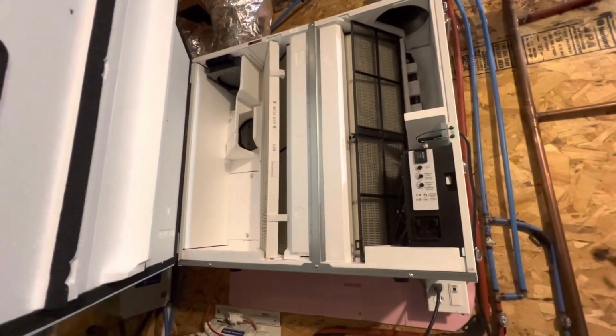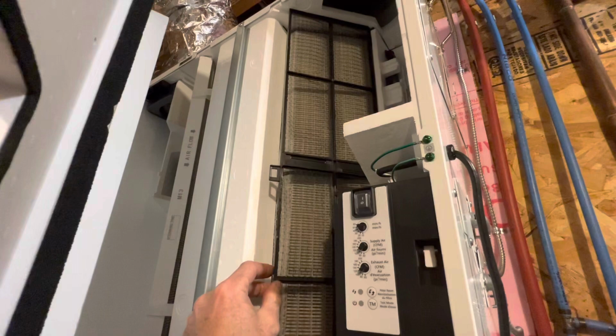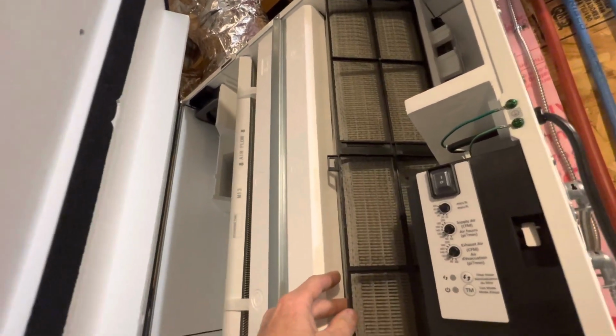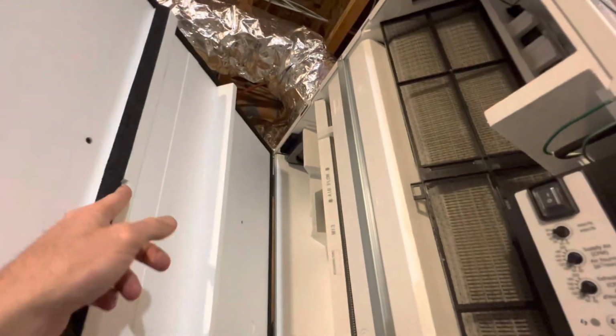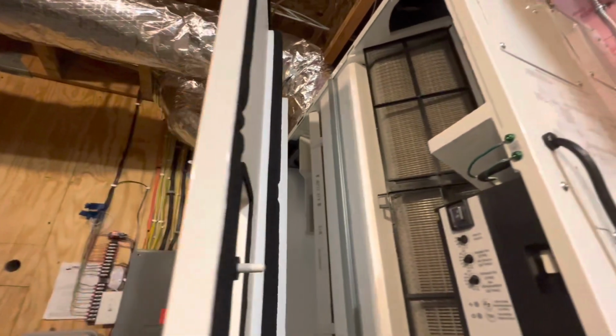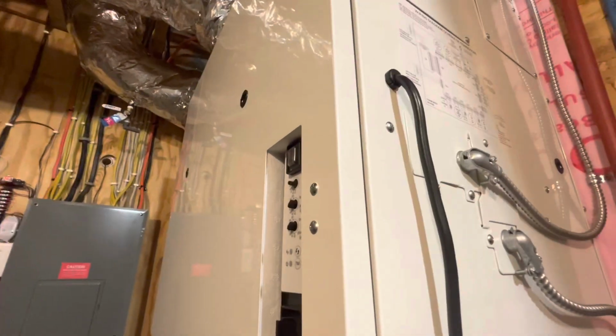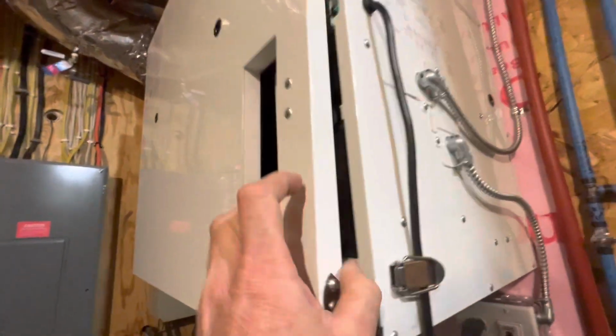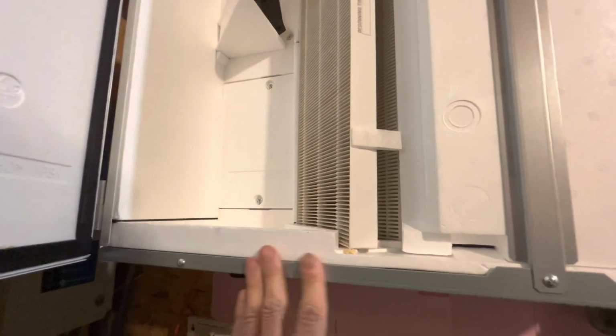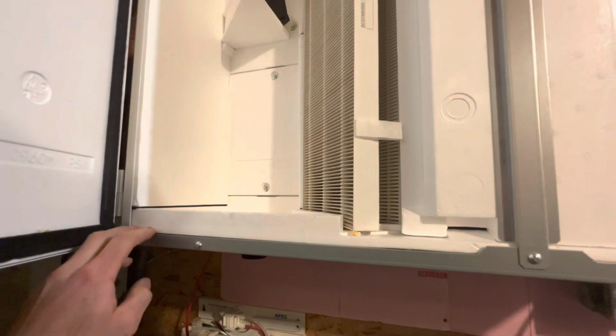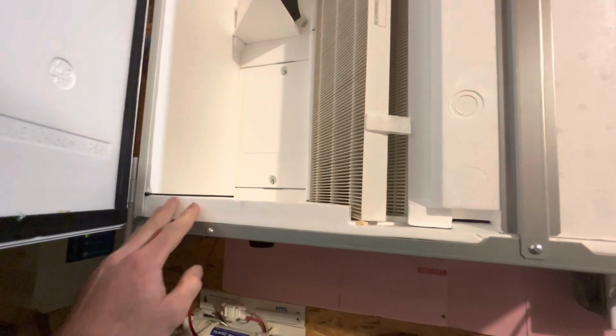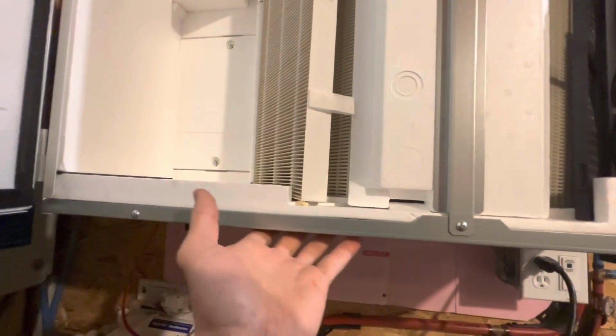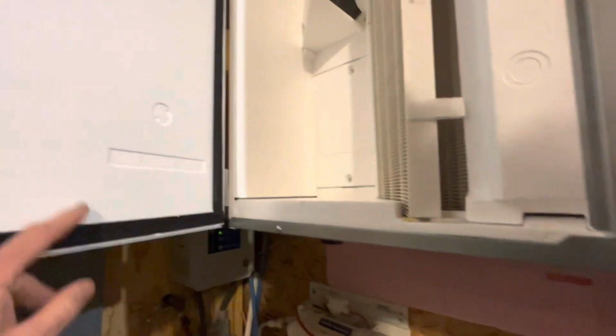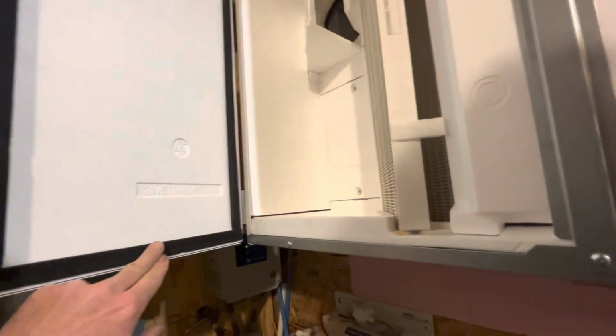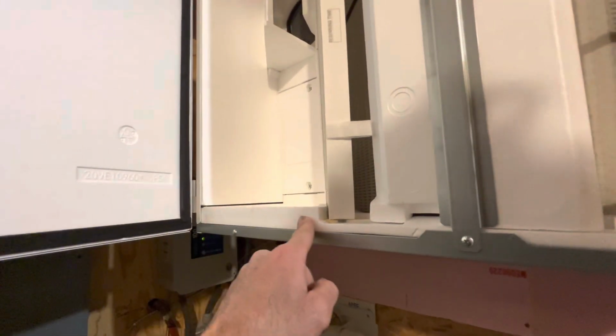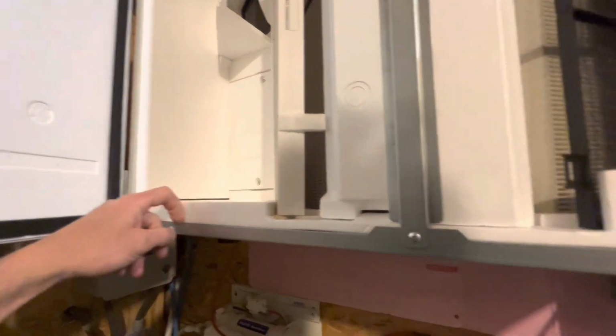One thing I have noticed on this door is this filter kind of likes to flex back and forth, so when you close the door, you've got to make sure that this little tab falls in that little slot in the styrofoam. So I'll close it. One more thing I've noticed is that when it's cold out, there really isn't any seal here. The cold air gets down to here and transfers to this. So if they were to change anything, or something I might add later, is to get another piece of foam like this and add it up a little higher so it seals here so that cold air can't get down to there.